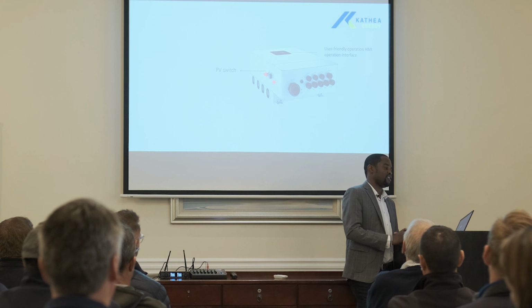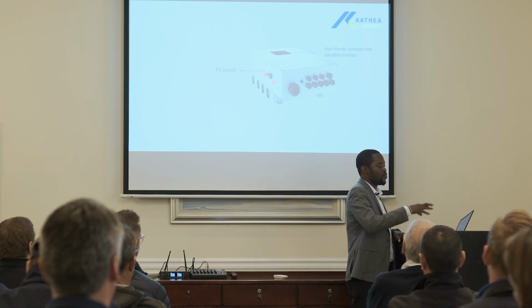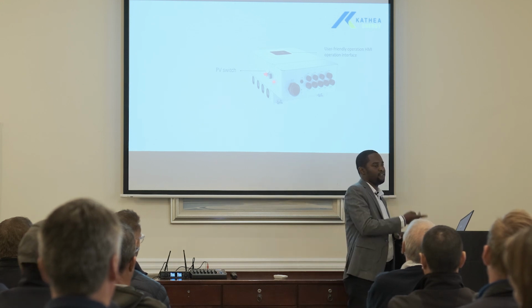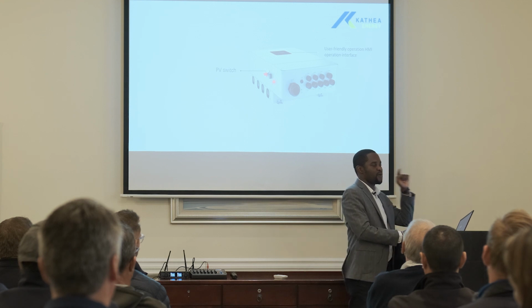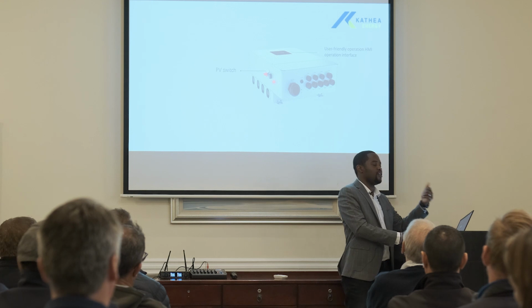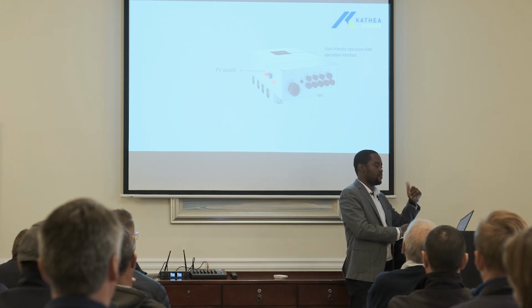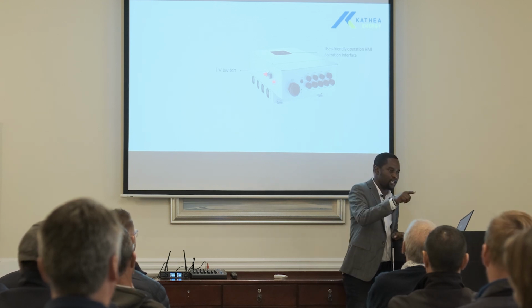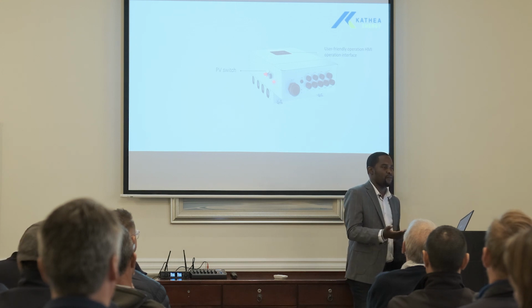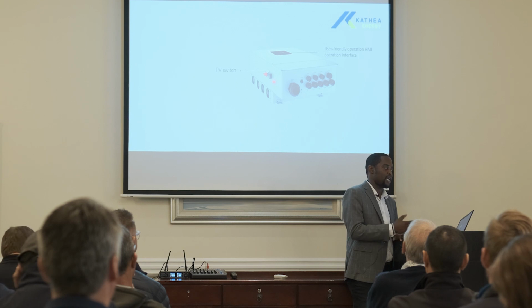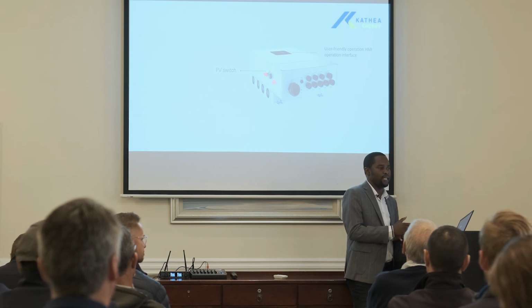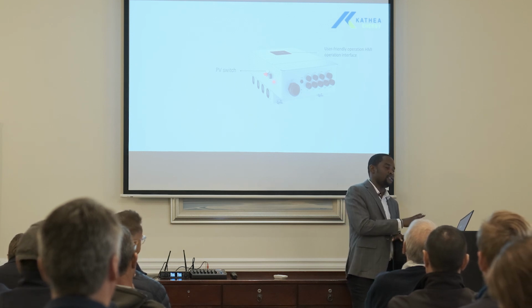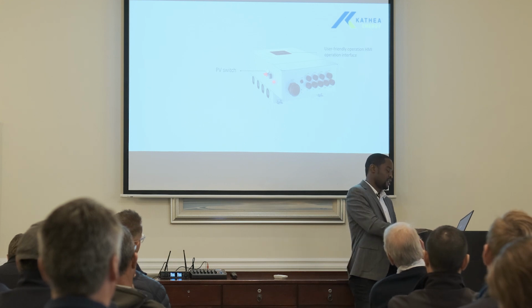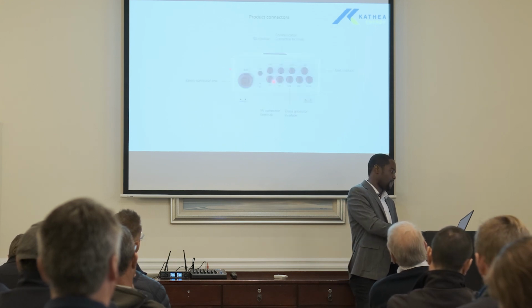The inverter is intelligent enough, after commissioning you can go to the system, then you deactivate that button so that even if someone comes and presses it on. So you've locked the padlock, you've got a padlock on the PV, then you also deactivate that button in the system so that even if a kid comes and is pressing there, nothing happens, the inverter continues working. So if you're supplying critical loads where you can't afford any power outage, then this switch and these functionalities become handy and they can give you more.